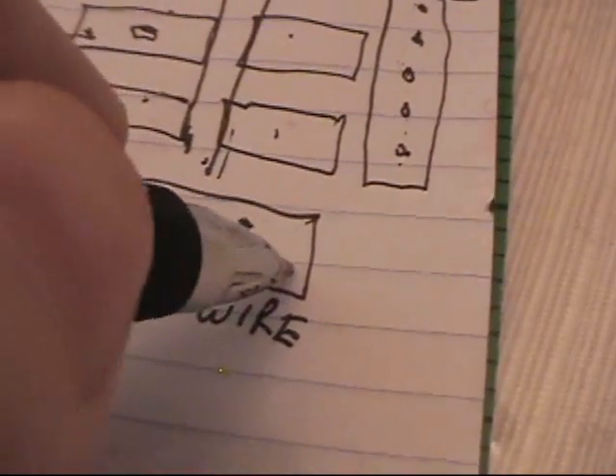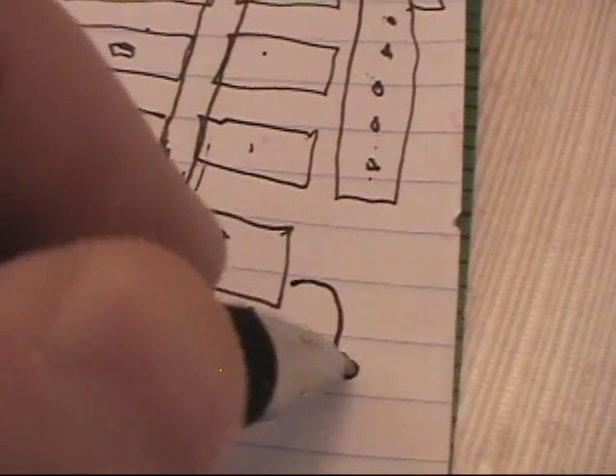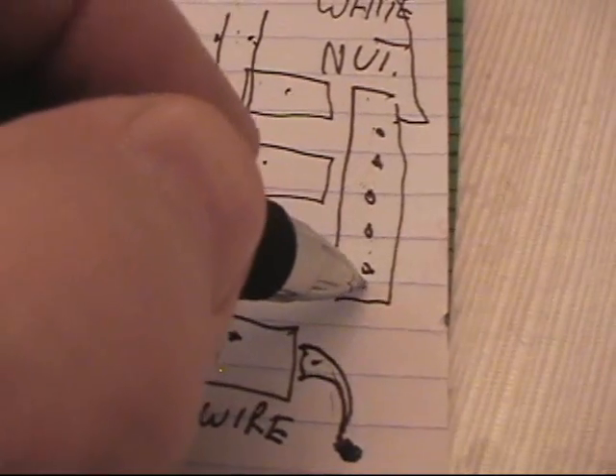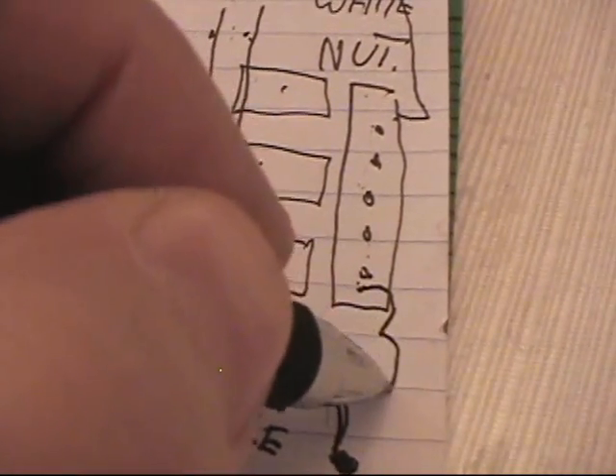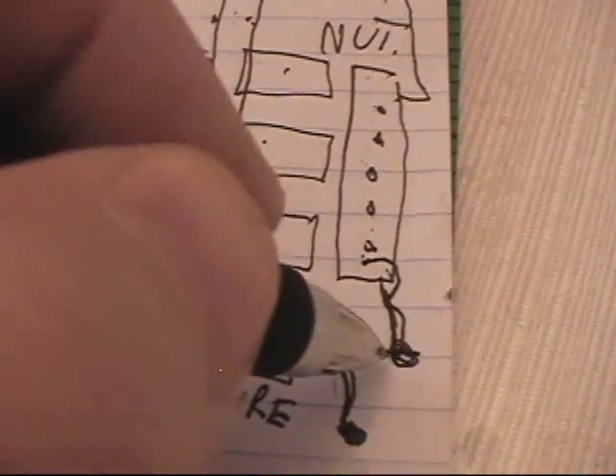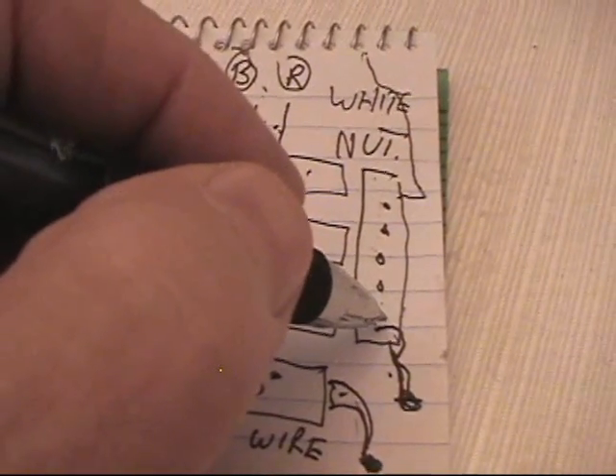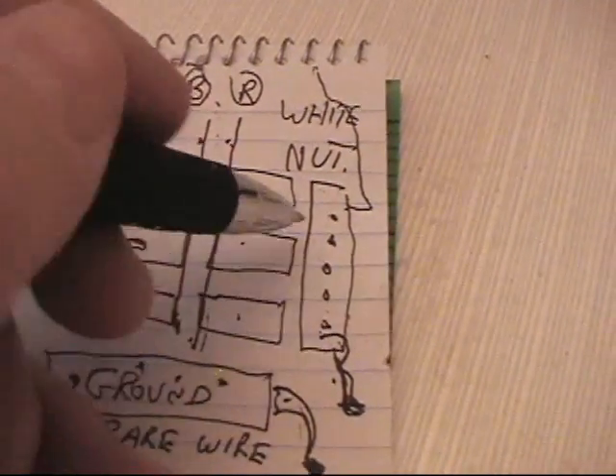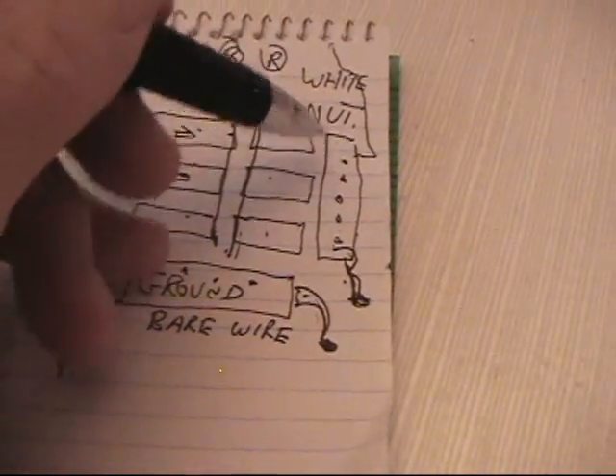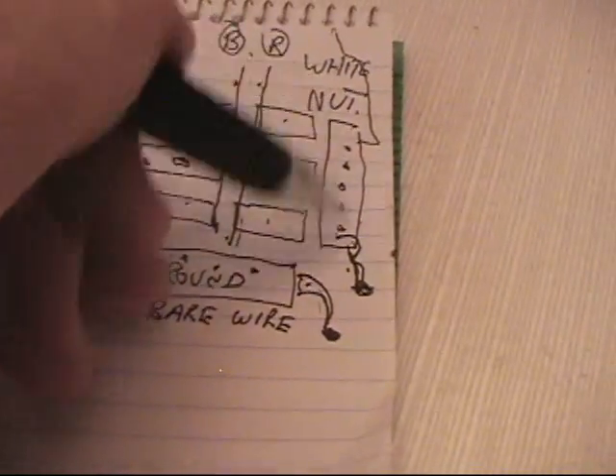Your ground, of course, is screwed to the panel, and it may have a tab also going down and screwing to give a ground. When you buy the panel, they have this little grounded tab for the neutral bar, too. Which, like I say, depending on the code, they may or may not require it. So you'll find that the neutral bar is sitting in an insulated little bracket, which is theoretically insulated from the panel box. But, depending on your location and the electrical code requirements for your city, that could vary.